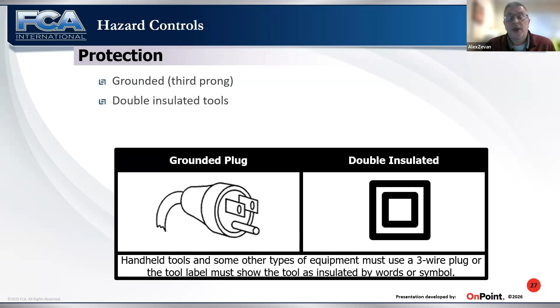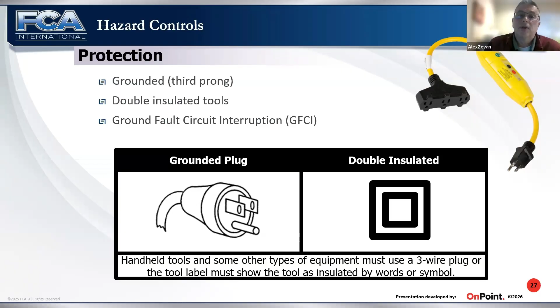And then the last, again, as we talked about with the ground fault circuit interruption, very, very important that we always think about this and actually use them at the source. We never want to take this GFCI pigtail and move it away from the source. We want to connect it to the closest available source that we can, rather than bypass that and connect it down the road. So here's some more quizzes.